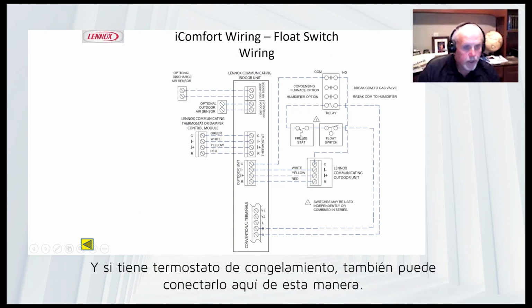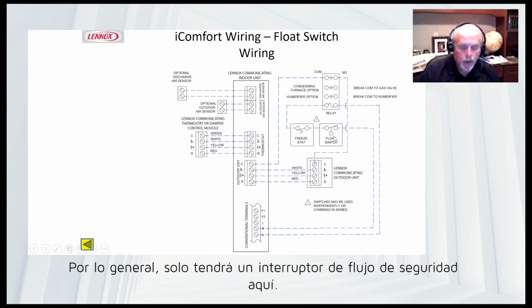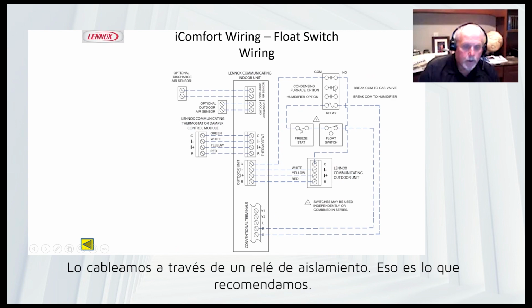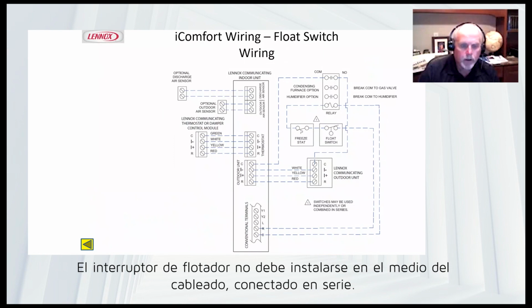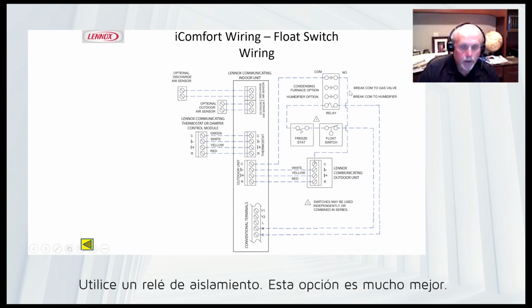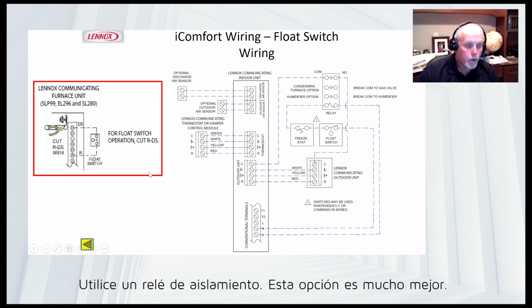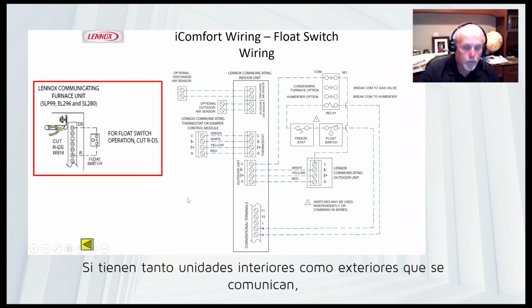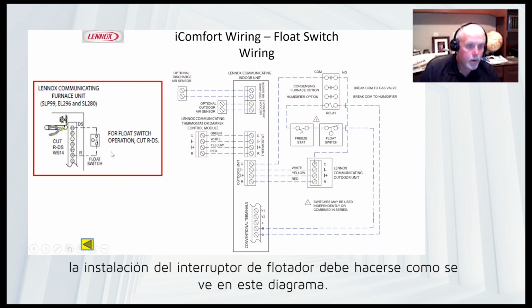switch. And if you have a freeze stat, you can also wire it in here like this. Okay, but typically you're just going to have a safety float switch here. We wire it through an isolation relay. All right, that is highly recommended. Do not just put the float switch in the middle of the wiring, wiring it in series. Use an isolation relay. That is much better. Okay, so if you have both indoor and outdoor units that are communicating, you would wire your float switch like this diagram.